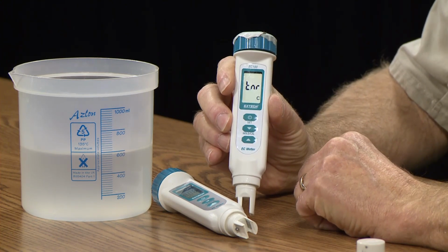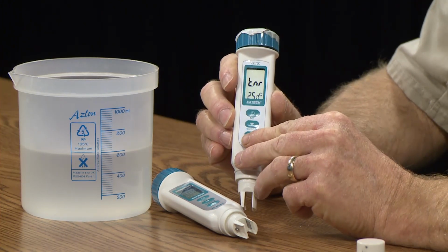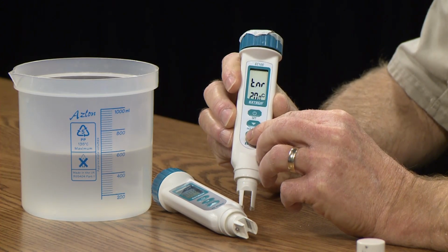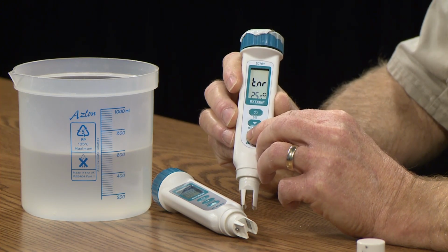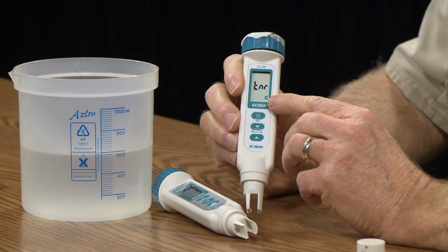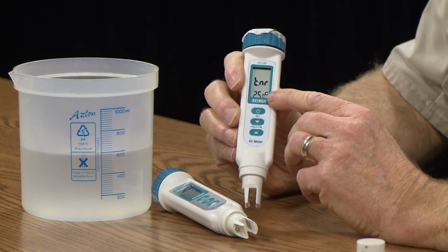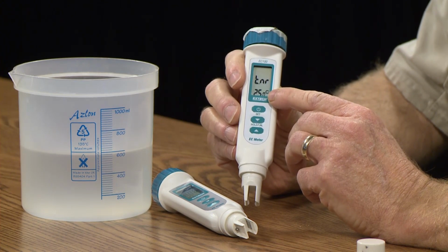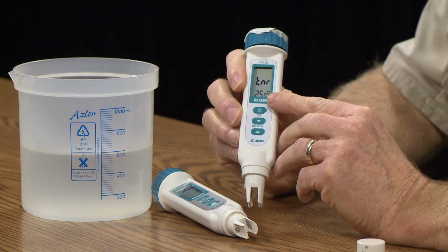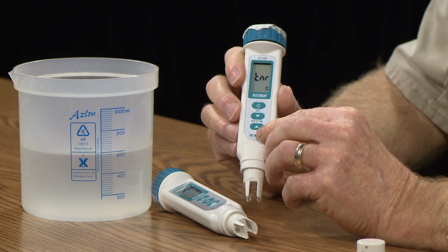Now I get this 25 degrees C. What is that? Well, let's just kind of fiddle around with it. I'm going to hit this button anyway, and there it goes, 20 degrees. Oh, so I have two choices, 25 degrees or 20 degrees. This is the specific temperature that you can set. So in this case, if you were taking specific conductivity, it would be referenced to 25 degrees. I could reference it to 20 degrees if I wanted to, but typically, more commonly, 25 degrees. So that's what that is. So this is set up for a specific conductivity to 25 degrees.